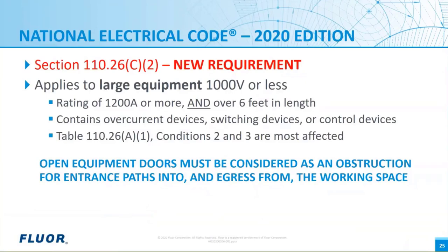The 2020 NEC contains a change found in section 110.26(C)(2) that's going to have a profound effect on electrical rooms and substation buildings. Table 110.26(A)(1) was well understood by everybody for many years, and it was simple to use, but now it's not quite as easy. Now, open equipment doors must be considered as an obstruction for entrance path into and egress from the working space. Please note this change only applies to large electrical equipment, 1000 volt nominal or less, 1200 amps and more, and that is longer than 6 feet.